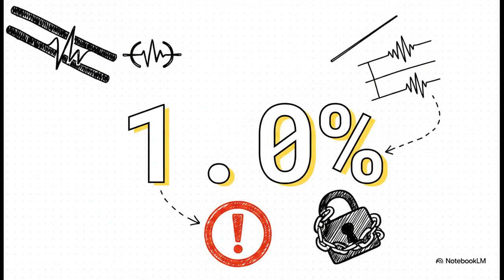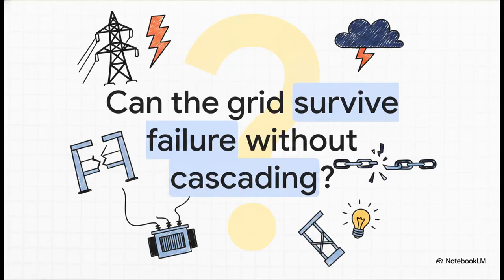Finally, we've got phase imbalance. This measures how evenly the load is spread across all three phases, and it's strictly capped at a maximum negative phase sequence component of exactly 1.0%. So we've fully mapped out the strict limits of steady-state voltage and power quality, but that leaves us with a pretty massive question. What happens to the grid when physical infrastructure suddenly breaks down? Can the network survive a sudden, massive equipment failure without cascading into a total blackout? We'll dive into exactly that next.